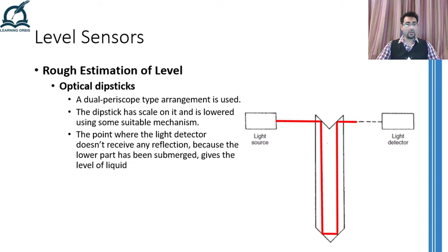There are four reflective surfaces so that light from the source is reflected in the shown path and received by the receiver. Using a suitable mechanism, the dipstick is lowered into the container to a point where the detector doesn't receive any reflection. This will happen when the lower reflecting surfaces are submerged into the liquid. At this point, the amount of lowering of the dipstick will represent the level of the liquid present in the container.